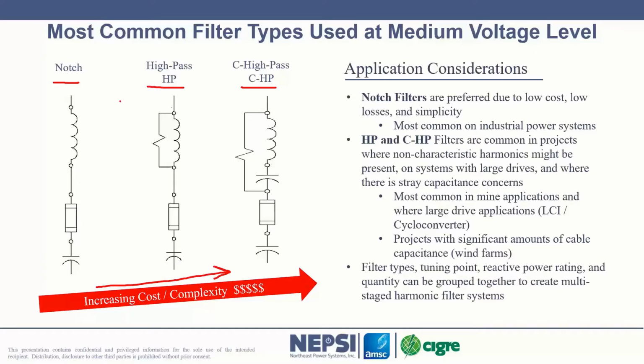So generally speaking, we are trying to use notch filters when we can, but if the situation calls for a different type of filter, we'll go to a high pass filter, and then for frequencies below the fifth harmonic, we'll go to sometimes a C high pass filter if we need to do a significant amount of dampening. So key here is we're dealing with a resistor across an inductor capacitor here, a resistor across the inductor here.